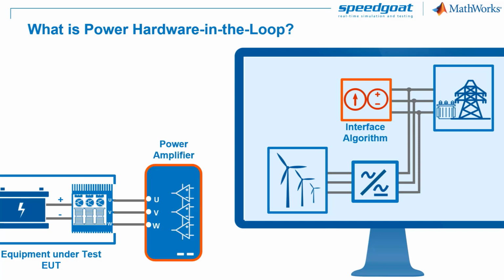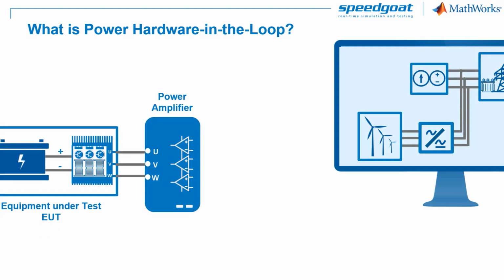We use a properly rated power amplifier to connect to the real hardware. By linking a power amplifier to the interface algorithm in real time, we can maintain roughly the same instantaneous power at the connection point with the electrical equipment, both in the simulation and in the real hardware. The link between the power amplifier and the interface algorithm is critical and should be very fast, at least as fast as the grid dynamics that we want to evaluate.